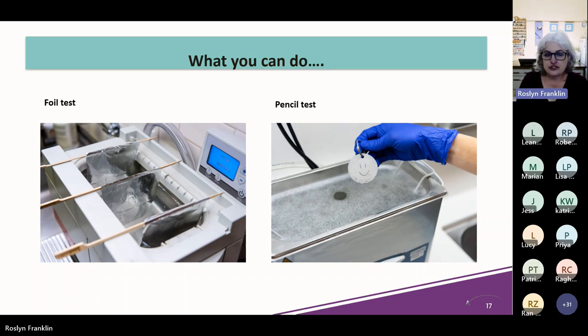Now this is after you have filled it, put your detergent in and degassed it. Then you do your test. After the 10 seconds is up, you take out each piece of foil and you're looking to see that there's little dents or holes evenly spaced in all of the pieces. What you might find is one particular piece looks like it's been hardly touched, and that's an indication that one of the transducers isn't working.